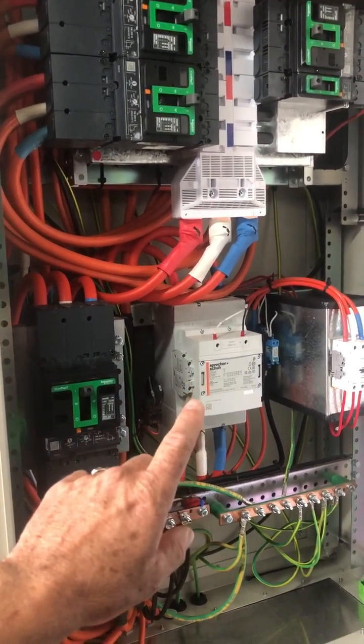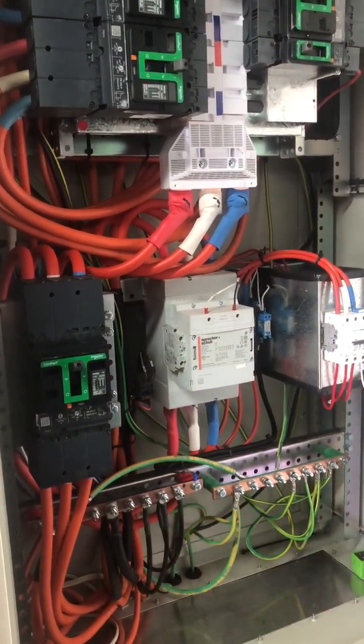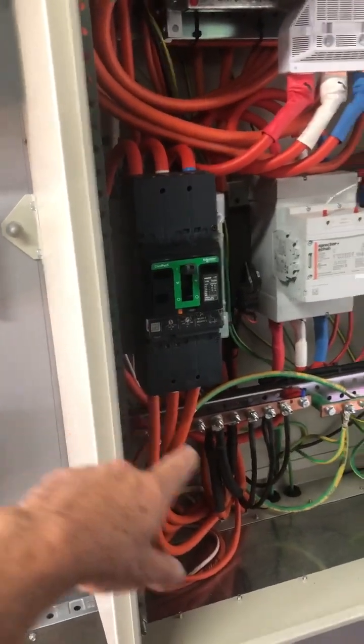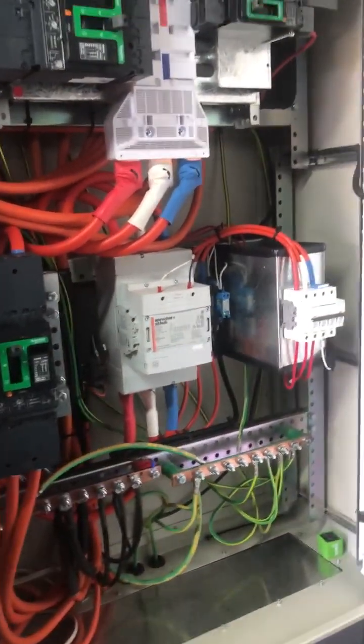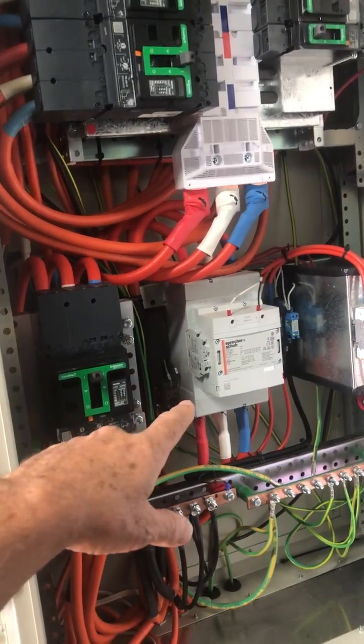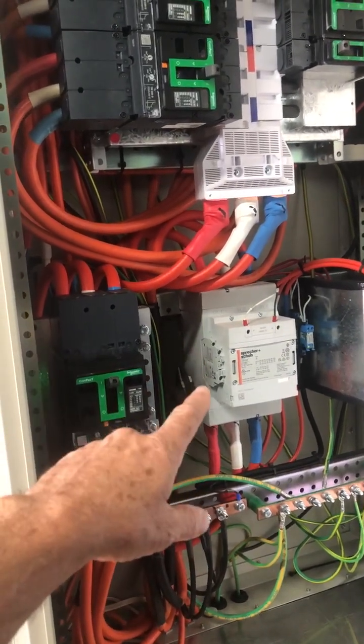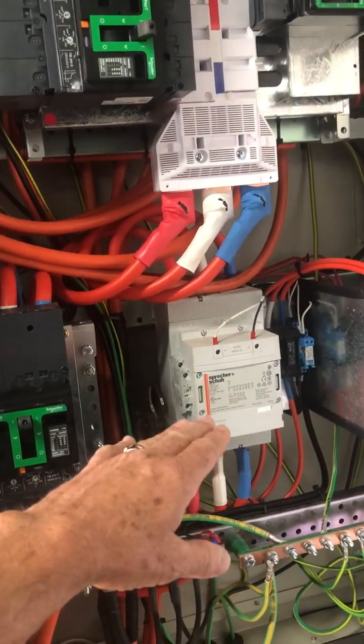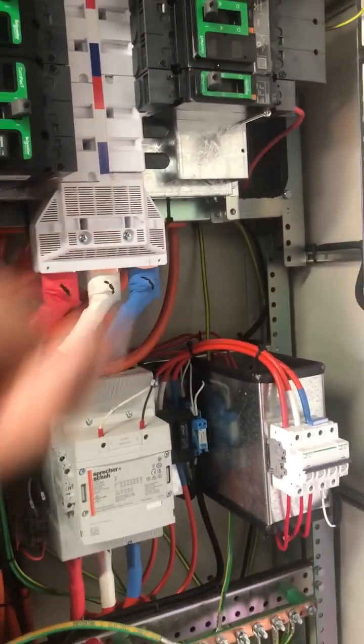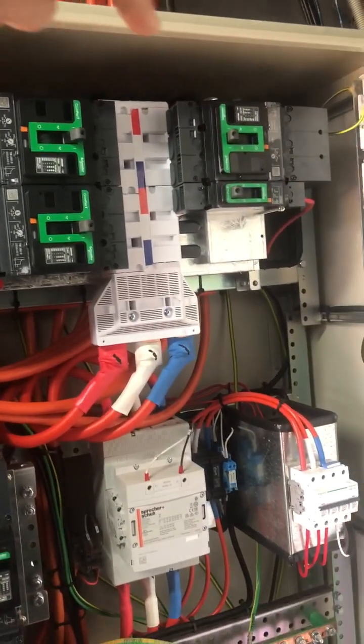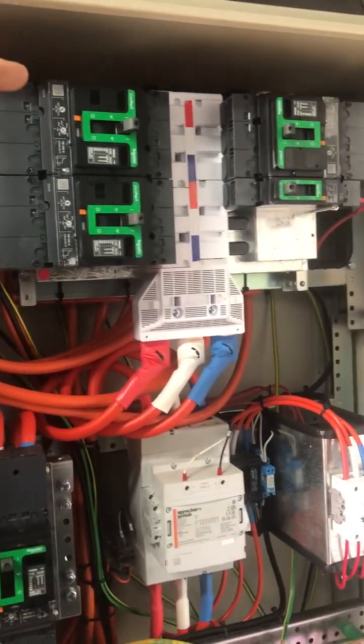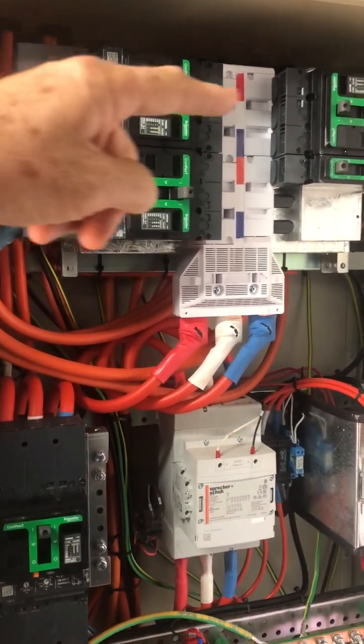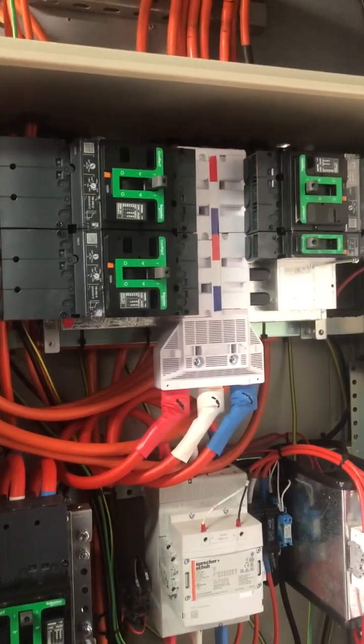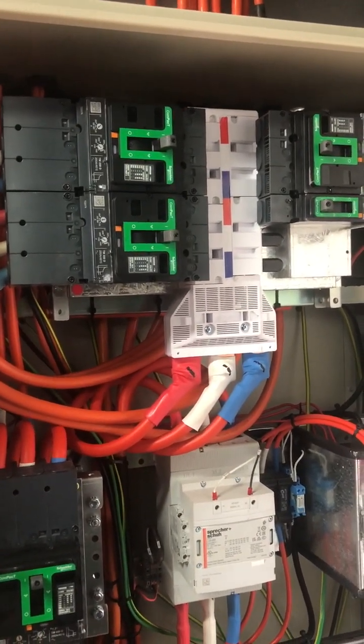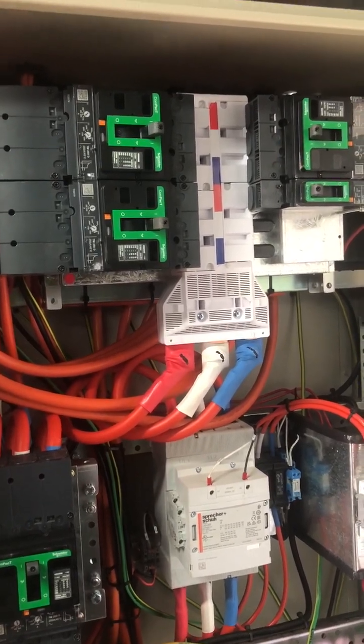And so when the generator is called, we can hear the generator switch on. We know there's power because we get a little signal over at the multi-mode inverters. After about 5 seconds, there's a synchronization going on. Then you'll hear this big contactor come in. What happens then is the generator is supplying power onto the AC bus, the inverters are supplying power onto the AC bus, and also the maximum power point tracking inverters, the Fronius inverters, are supplying power onto the DC bus.